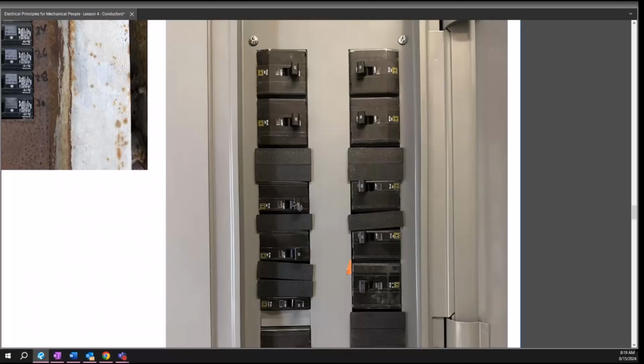However, on a 240 high leg, I have been known to actually put a 208 single phase hot water heater — neutral to ground. It's a 120/240 panel board, and I had 208 because of the high leg, and that's the only hot water heater we could get. It technically works, but there's more math that has to be done outside of the normal panel schedule — more stuff you have to contend with. So technically yes, but unless you know exactly what you're doing and understand the math, don't do that.